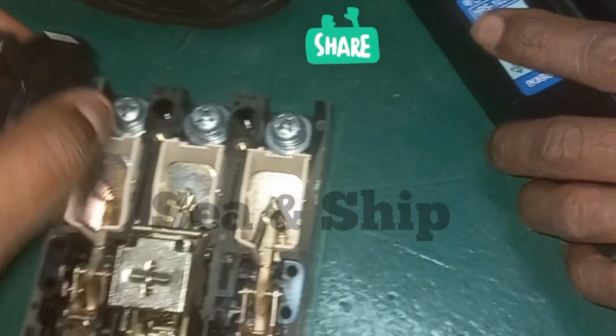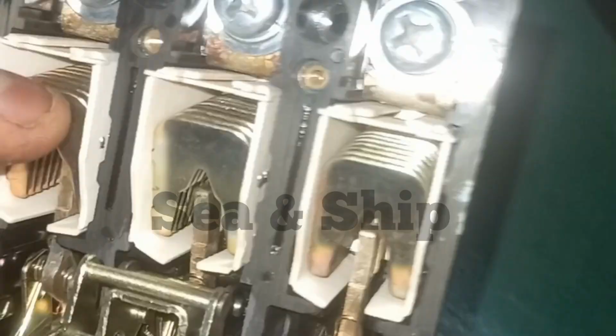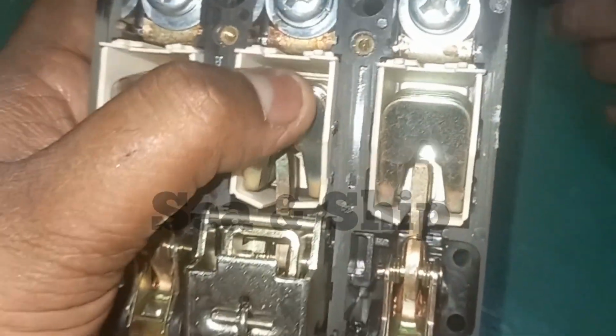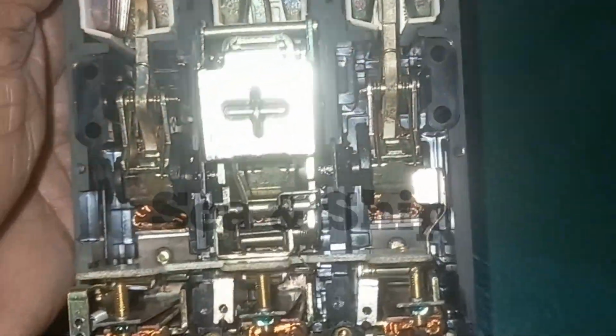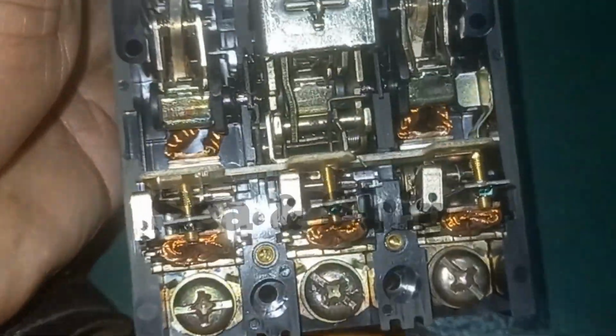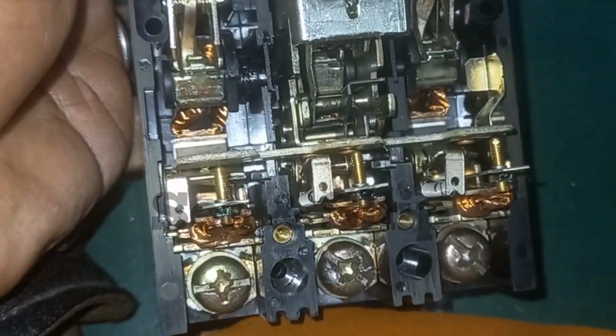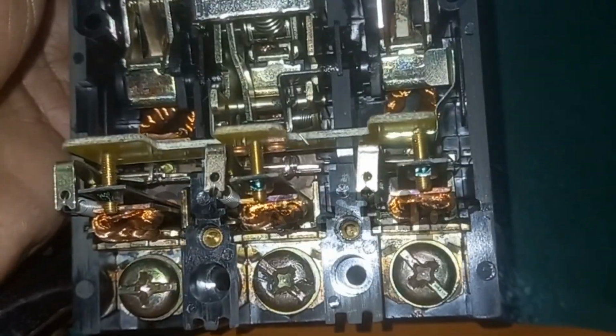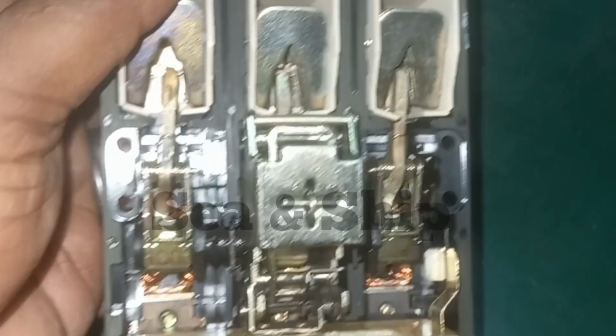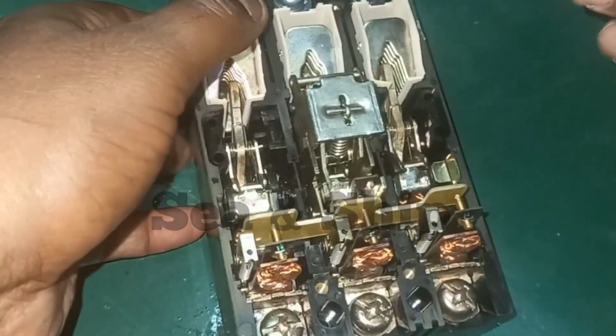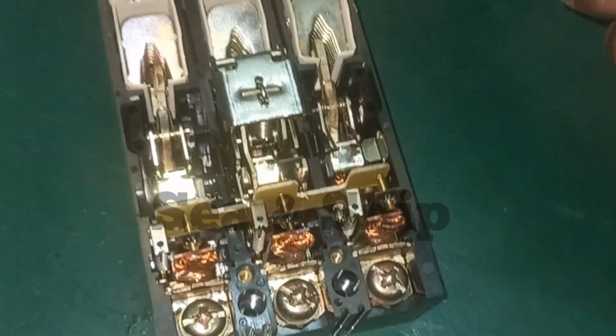As marine engineers, MCCB maintenance is part of our PMS. Every month, do a visual check. Look for any hot spots, loose connections, or burning smell. Clean the dust. Every 3 months, do a manual ON-OFF test and a push-to-trip test to make sure the mechanism is free.